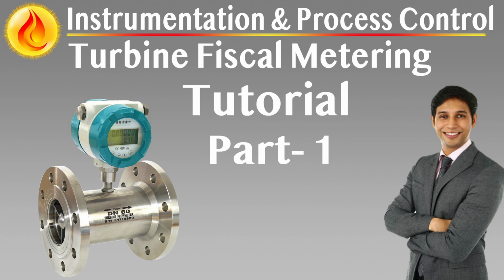Calibration records and audit storage. Every calibration, adjustment, or change to measurement parameters must be documented and stored securely for the duration required by law or agreement. These records must be easily retrievable and structured to support external audits. Parameters such as calibration factors, drift data, instrument replacement, and deviation trends must be included in a centralized database accessible to approved parties. This reinforces system accountability and enables forensic analysis in the event of discrepancies.